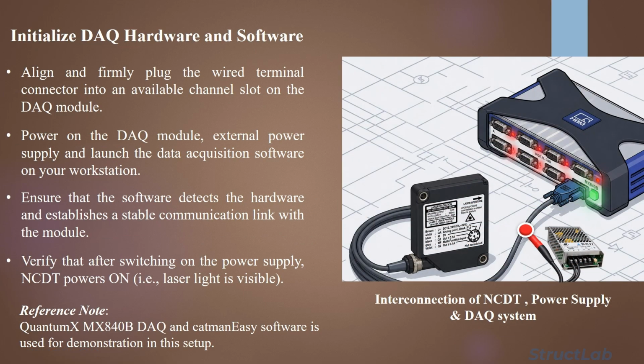Step 5. Initialize the DAQ hardware and software. First, align and firmly plug your wired terminal connector into an available channel slot on your DAQ module. Next, power on the DAQ module and external power supply. Then launch your data acquisition software on your workstation. Ensure that the software automatically detects the hardware and establishes a stable communication link with the module. Also, verify that the NCDT sensor powers on successfully after switching on the external supply, which you can confirm by checking that the laser emission light is active. Please note, for this demonstration, we are utilizing the QuantumX MX840B DAQ module and catmanEasy software.